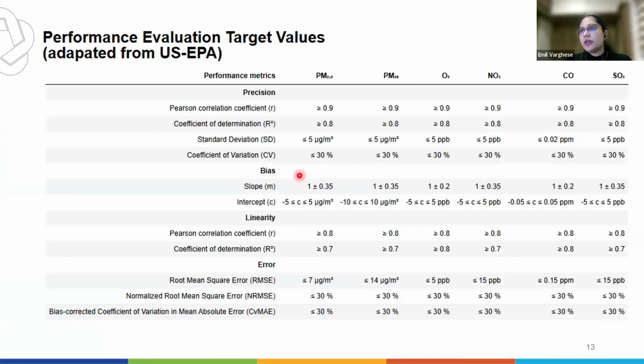Now, as I mentioned, I'll be talking about the target values. USEPA generally uses these target values on a daily average, but we have considered them on a 15-minute as well as 1-hour average, and we have come to these particular numbers which can be used to look into the sensor performance. When we consider, say, PM2.5, if you want to check the precision among the inter-unit devices for a batch, your R value should be greater than 0.9, R square greater than 0.8, standard deviation less than 5 micrograms per cubic meter, and the CV value less than 30%. If these 4 criteria are met by that particular batch of sensors, then we can say that the PM sensors in that batch are precise to each other.